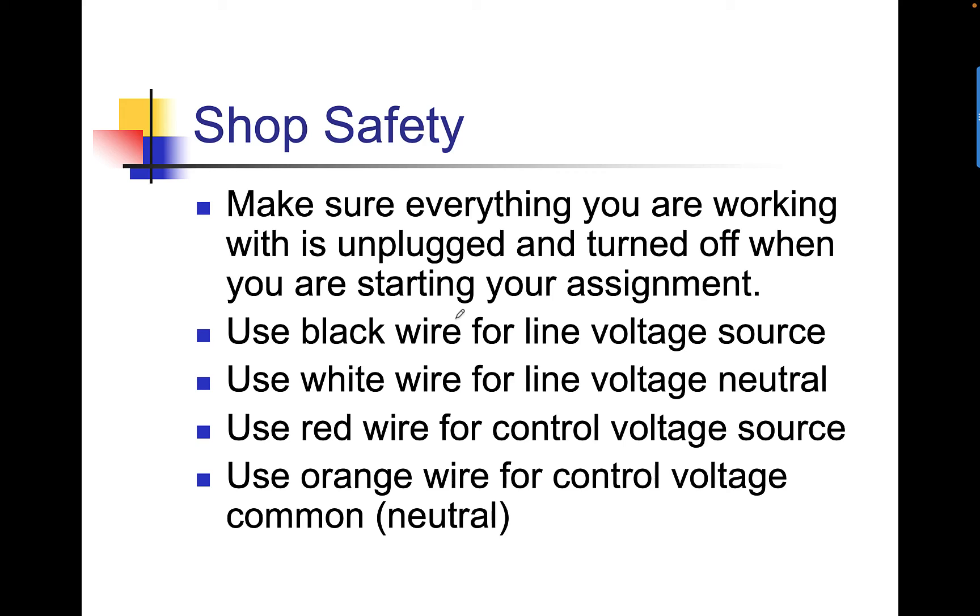If you're in a shop environment or if you're working on this stuff on your own time just to learn it, make sure everything you're working on is unplugged and turned off when you're starting any lab work. Try to use a black wire for line voltage source, use a white wire for line voltage neutral, and use a red wire for control voltage source and an orange wire for control voltage common, which is the equivalent of neutral. There's some different terminology for the control voltage.